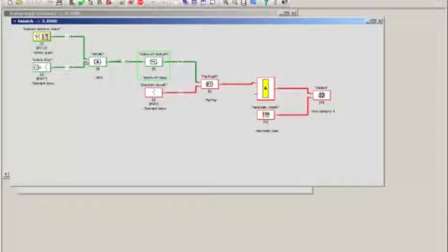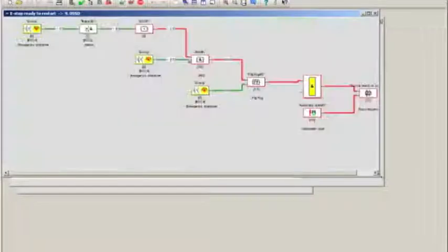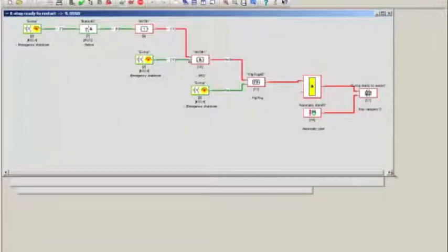There's another sheet here in the background that I would like to discuss, and this is associated with OSSD9. There is no such thing as a physical output number 9 on this device. What I use this for is to provide feedback to the PLC that signals when the e-stop is in the ready-to-be-reset state.